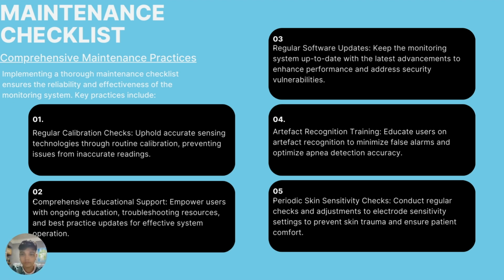Next up, the artifact recognition training is to educate users on artifact recognition to minimize fake alarms as well as optimize apnea detection accuracy. For the last one, the periodic skin sensitivity checks, users can conduct regular checkups and adjustments to electrode sensitivity settings to prevent skin trauma as well as to ensure patient comfort.